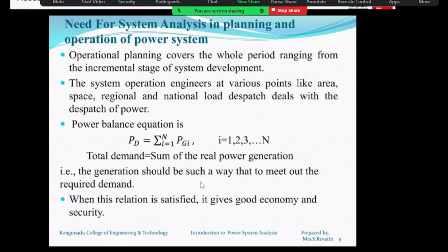Because if suddenly demands increase, if suddenly loads increase on the power system, then what will we do? If the load will suddenly increase on the power system and we don't have extra power in reserve, it will cause the frequency to go down. If frequency goes down from the nominal value, then it will cause the generators to shut down one by one. Then overall blackout can happen. So the power entities or power producers keep the power generation higher as compared to the required demand. Like they keep some power in reserve. So if suddenly load increases, then they can supply that reserve power to that load.